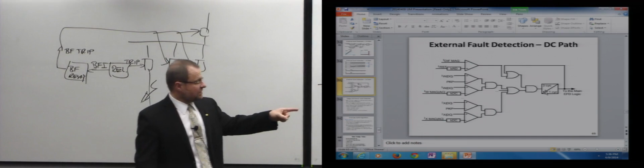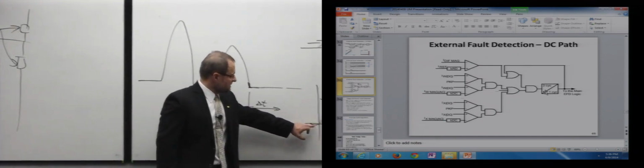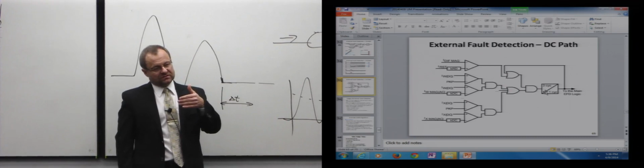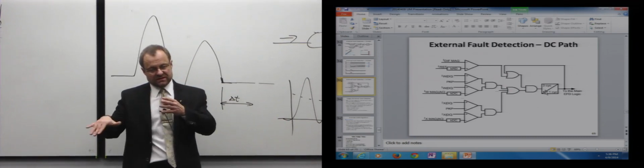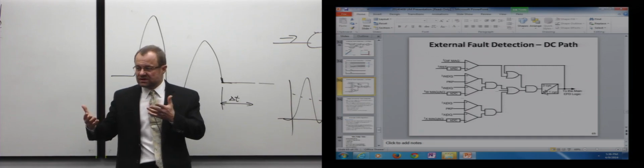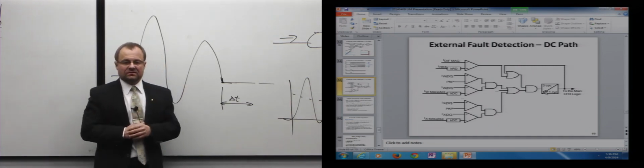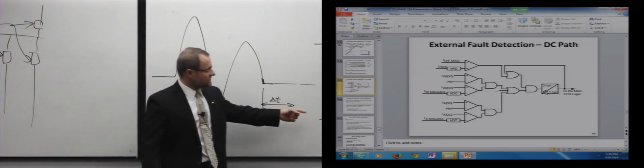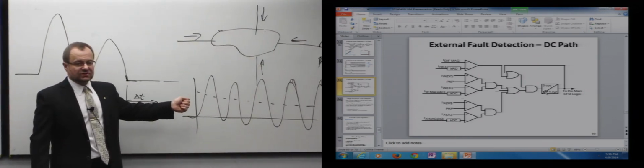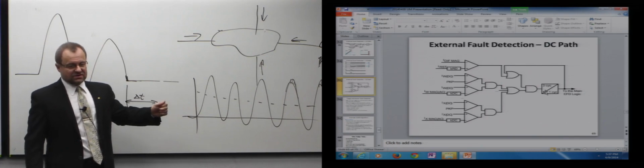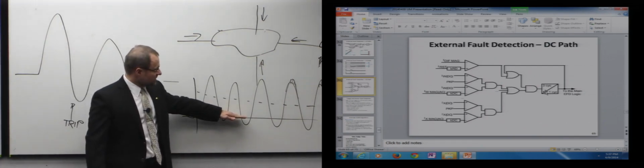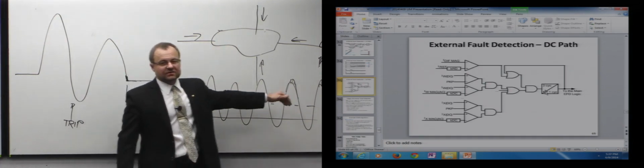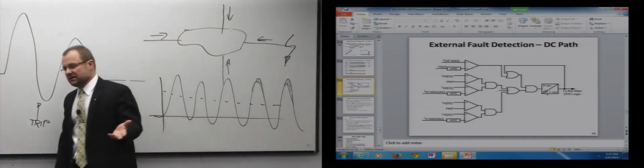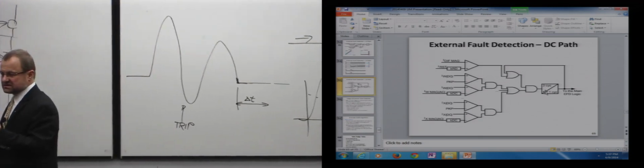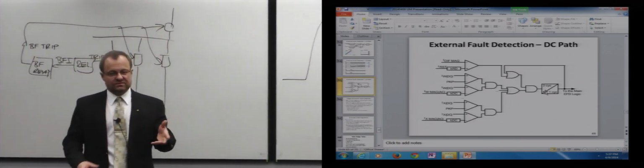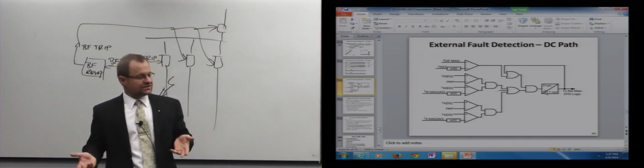And this happens very often on generator relays because near generation, your X over R ratio that dictates that DC time constant is huge. It's 90 or 70. It also happens on generators when you pick up a transformer. When you pick up a transformer, it draws an inrush current. Inrush current is not bidirectional. It's offset, and it could last for a second. So recently, NERC mandated the black start exercises, meaning that you assume that there is a blackout and you restore the system to normal.